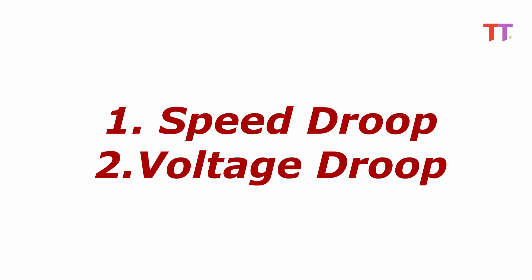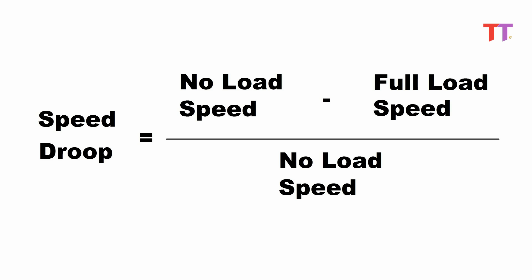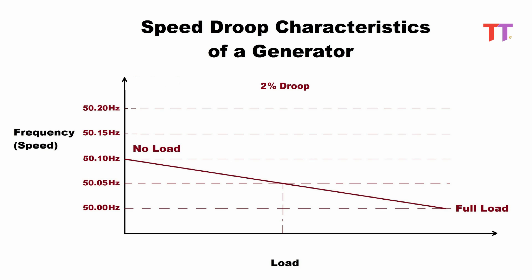There are different types of droops — first, speed droop, and second, voltage droop. We will discuss speed droop setting in the governor of the generator. The formula for droop is: no load speed (or frequency) minus full load speed, upon no load speed. This is the speed droop characteristic of a generator.